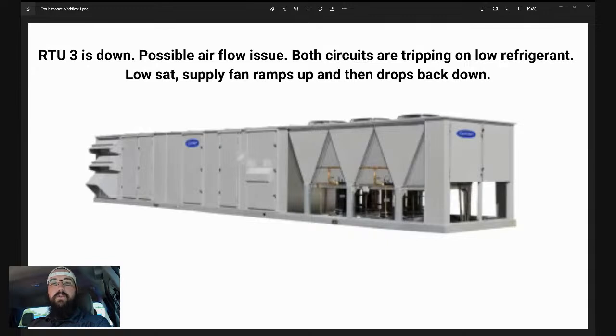So what's restricting me downstream on the airflow side? Why are we having to ramp the fan down so much? Now, the fan running to 60 hertz right out the gate and then backing down, that should be normal. The fan is going to ramp up to try to meet static set point. It's got a control PID on that speed that's going to do that. So I would expect that. That's fine.